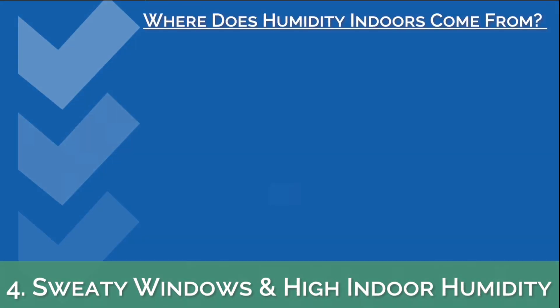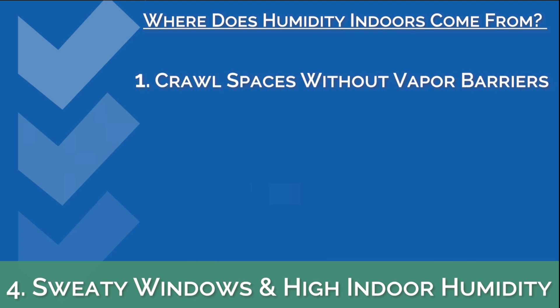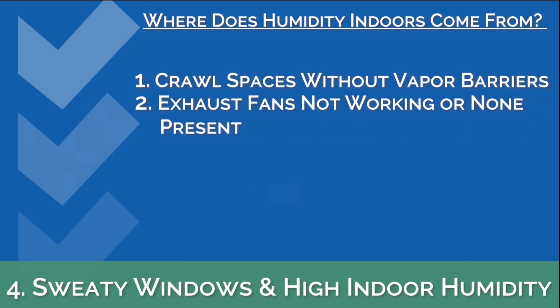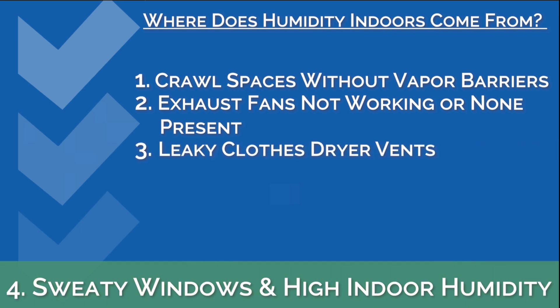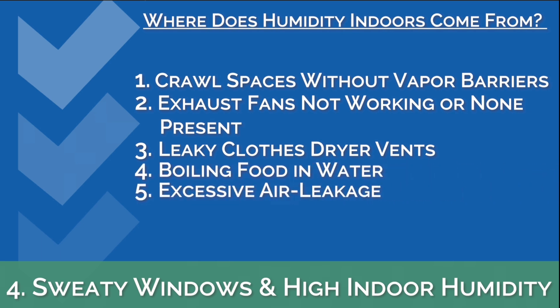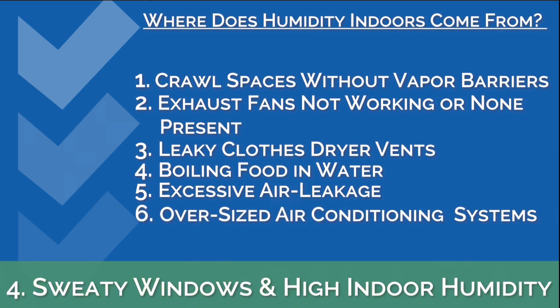So where does all this humidity come from inside the house? The most common sources of humidity are crawl spaces and cellars without vapor barriers over the ground, bathroom and kitchen exhaust fans not working properly or no fans at all, leaky clothes dryer vents, boiling food and water, excessive air leakage to and from attic spaces, crawl spaces, and outdoors, and oversized air conditioning systems.